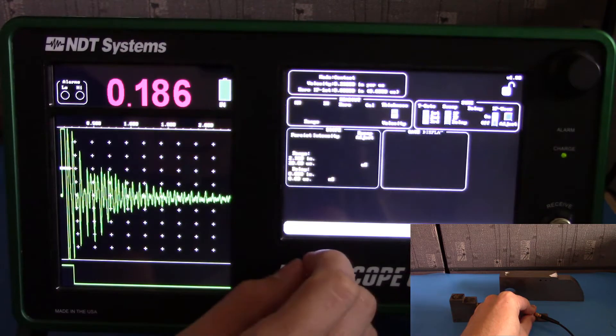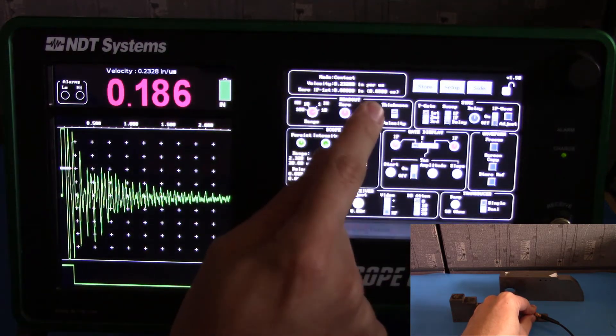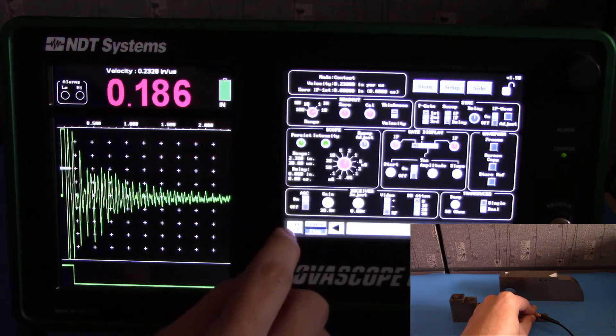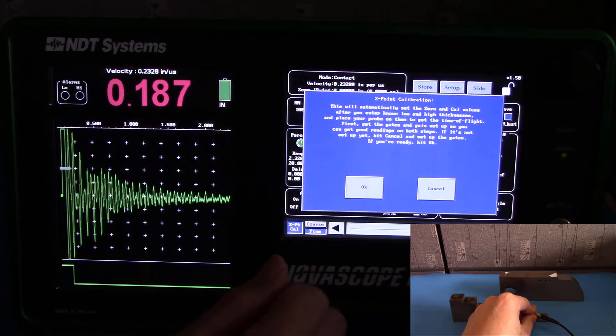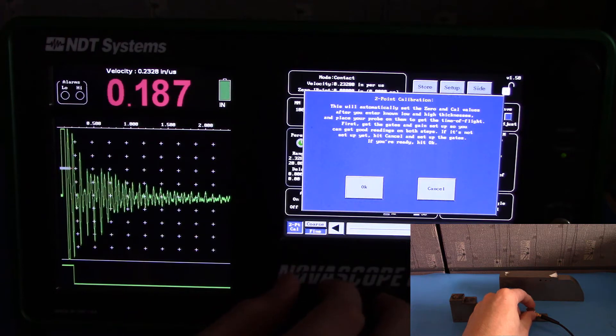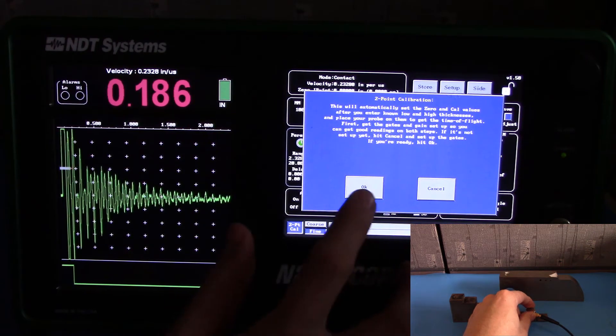Next, go back to the front. Go to the Cal radio button. And go to the 2-point cal selection that appears in the bottom left. This is where we will set up our 2-point calibration on the probe. Go ahead and hit OK.